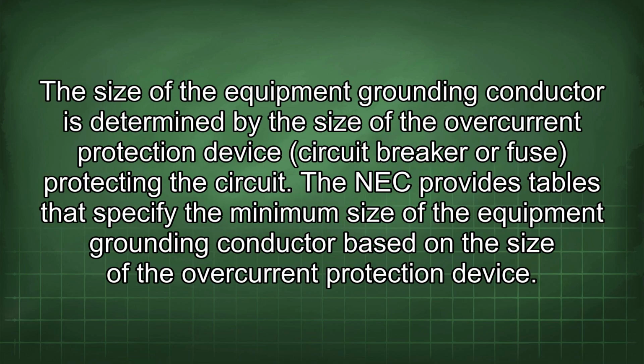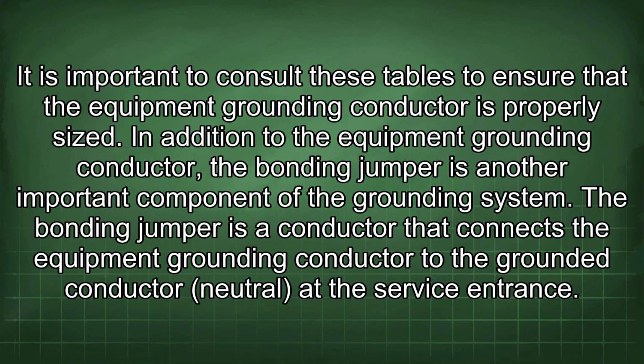The size of the equipment grounding conductor is determined by the size of the overcurrent protection device, circuit breaker, or fuse protecting the circuit. The NEC provides tables that specify the minimum size of the equipment grounding conductor based on the size of the overcurrent protection device. It is important to consult these tables to ensure that the equipment grounding conductor is properly sized.